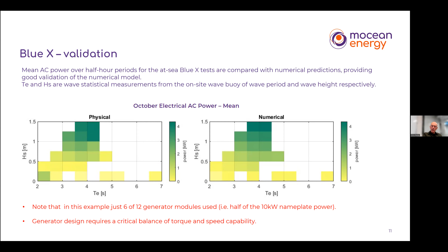We had a generator which was composed of 12 generator modules, and we could connect these all in series to give us high voltages. It turned out, in fact, that the voltages were too high in the very largest seas, so we had to reduce the number of modules, and we didn't have any more sophisticated method of connecting those modules. Had we connected them in series parallel, in other words, we would have had a half generator of 6 modules plus another half generator of 6 modules, we could have generated twice the power. So we proved to our own satisfaction that the 10 kilowatt generator was indeed capable of generating 10 kilowatts. But the lesson learned here, the important lesson learned, was that generator design is a critical balance of torque and speed capability and must be matched to the environmental conditions.